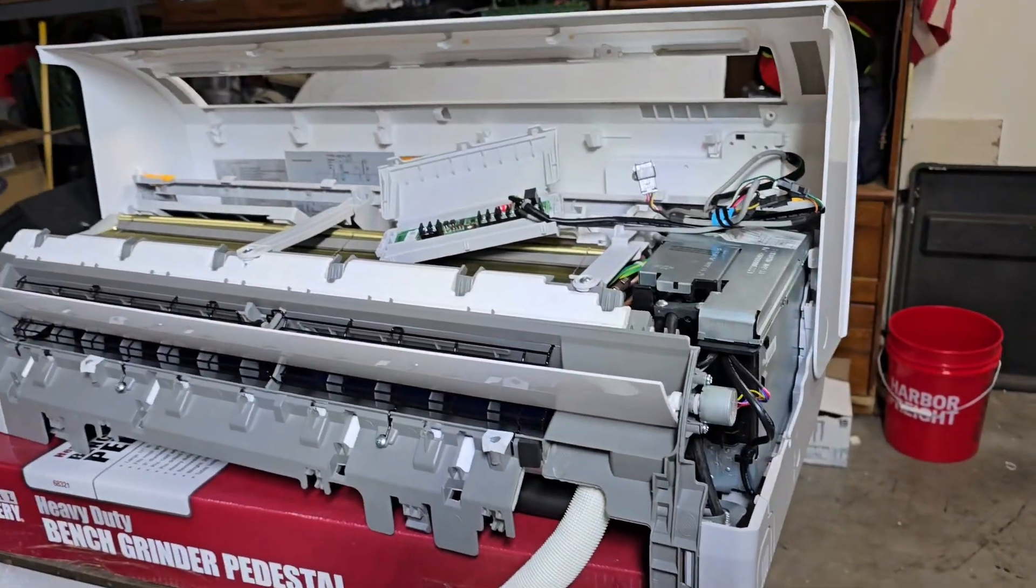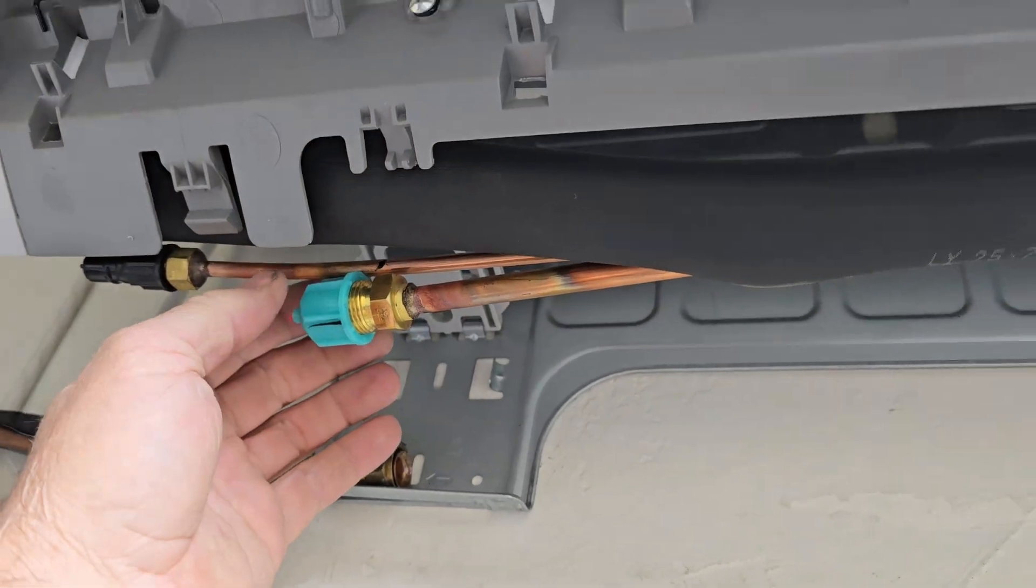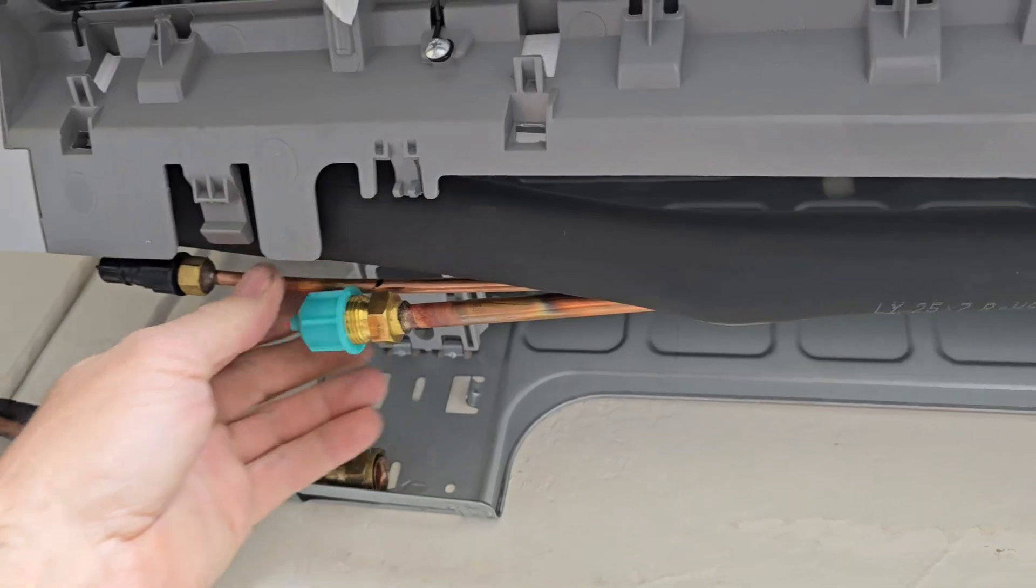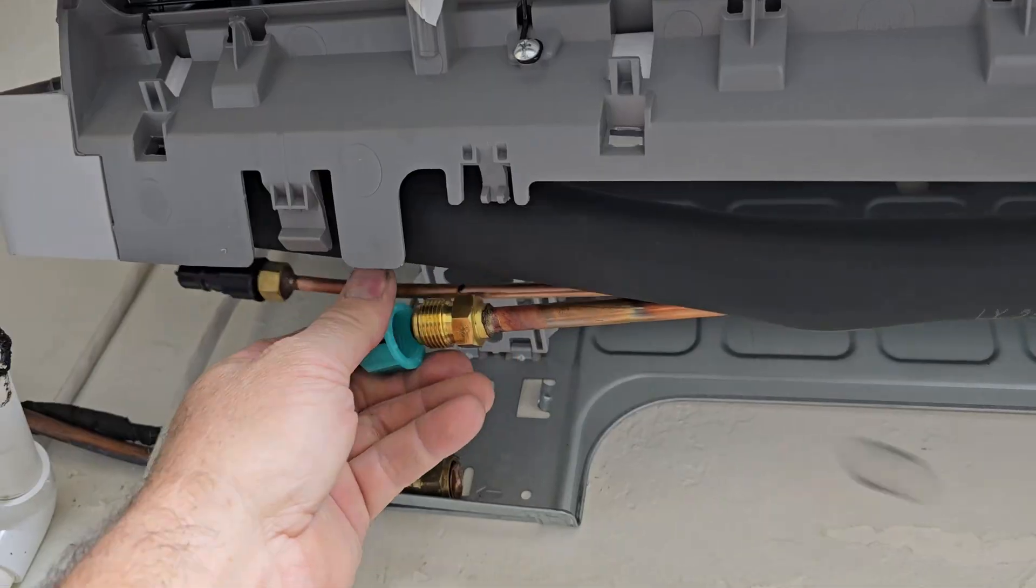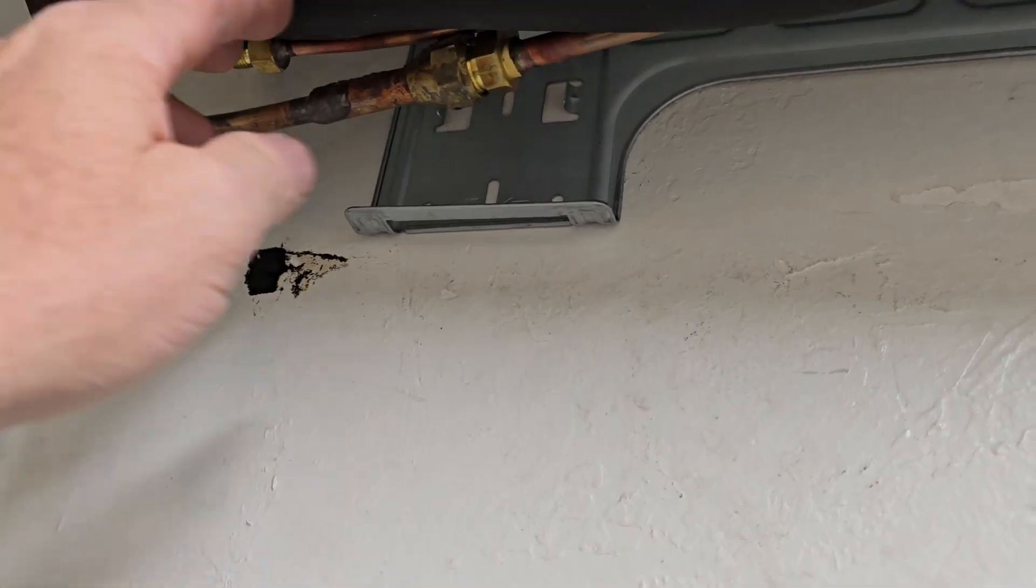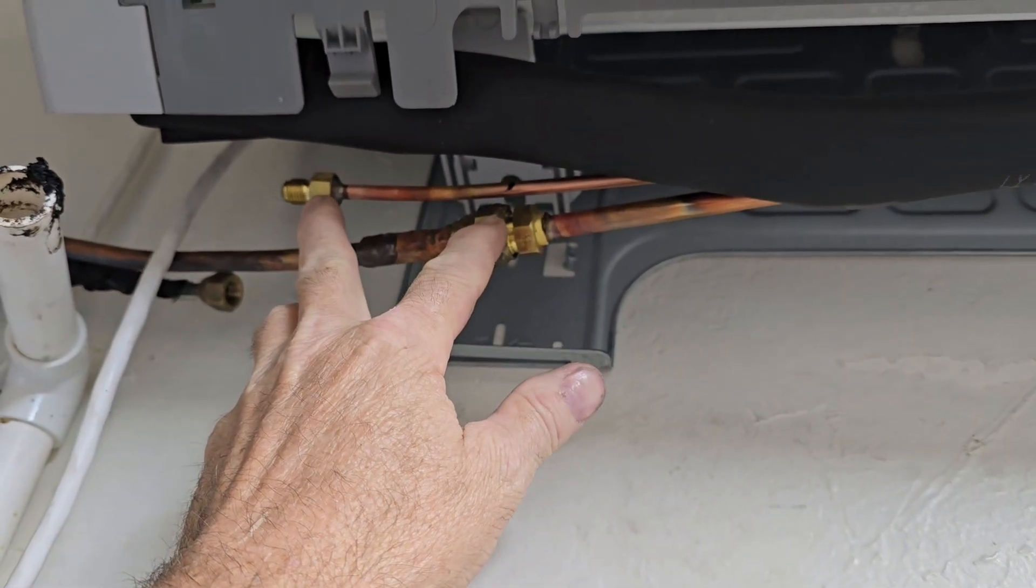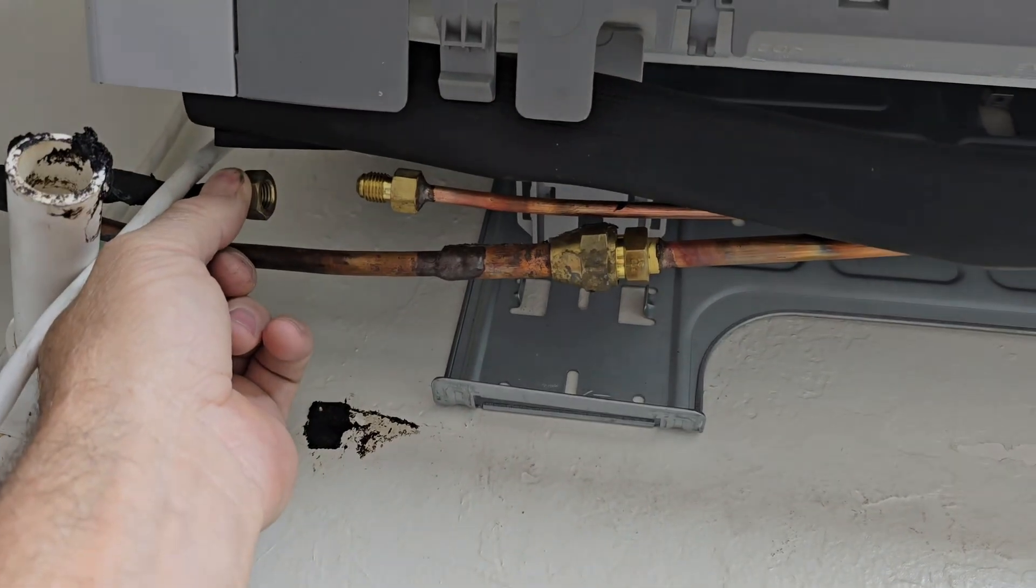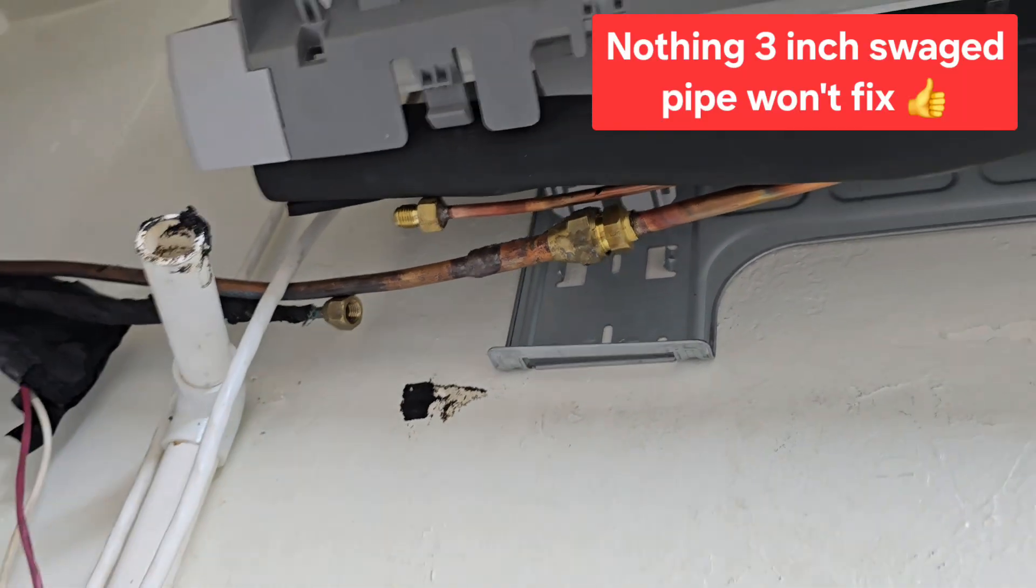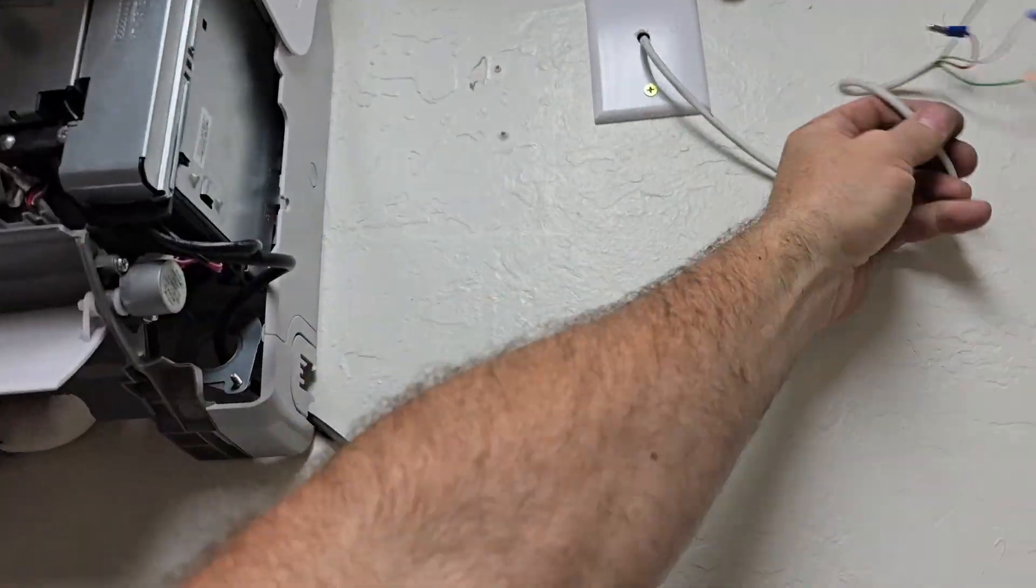I just started unthreading these. That's good when a four-year-old unit still has nitrogen in it. It's just going to connect right back up to my line, so this is actually going to try to be a real easy change out. I spoke too soon. These pipes are not staggered the same as the one I just took off. Look at this, there's a two and a half inch gap. I have to extend that.